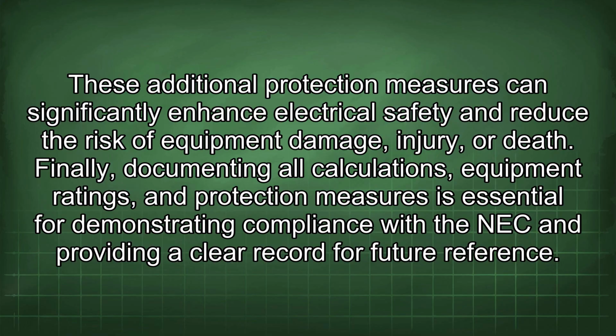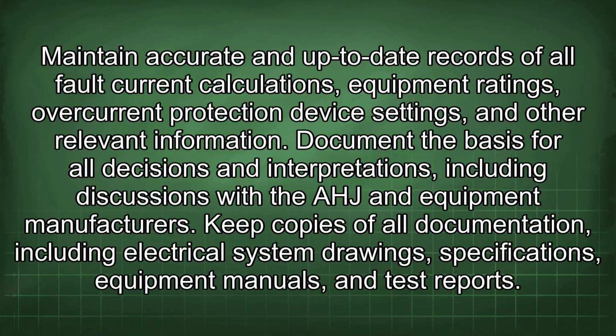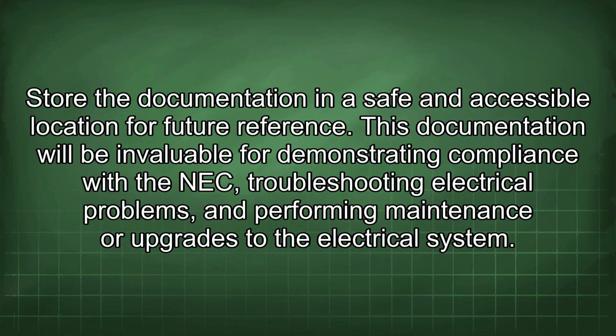Finally, documenting all calculations, equipment ratings, and protection measures is essential for demonstrating compliance with the NEC and providing a clear record for future reference. Maintain accurate and up-to-date records of all fault current calculations, equipment ratings, overcurrent protection device settings, and other relevant information. Document the basis for all decisions and interpretations, including discussions with the AHJ and equipment manufacturers. Keep copies of all documentation, including electrical system drawings, specifications, equipment manuals, and test reports. Store the documentation in a safe and accessible location for future reference.